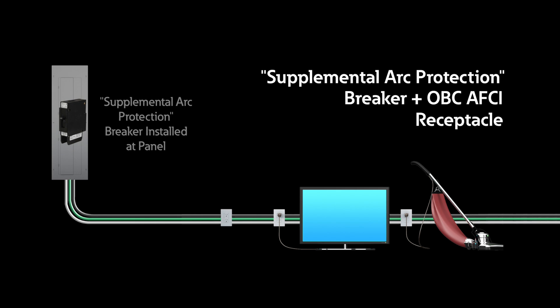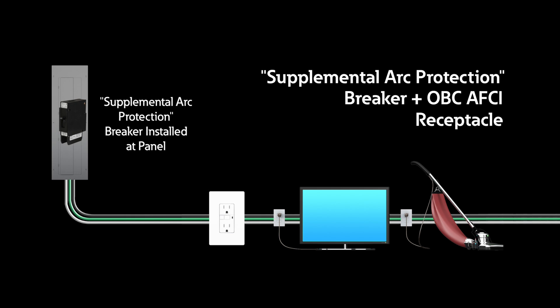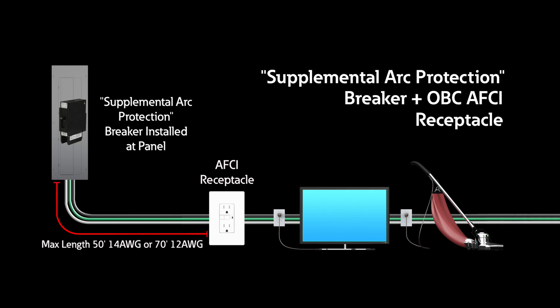Supplemental arc protection breaker with an OBC AFCI receptacle. This method allows for a listed supplemental arc protection circuit breaker to be installed at the origin of the branch circuit in combination with a listed AFCI receptacle installed at the first outlet box on the branch circuit. While this allows for local reset capabilities, supplemental arc protection breakers are not currently available. Additionally, there are limitations in the home run length and the circuit must be continuous.